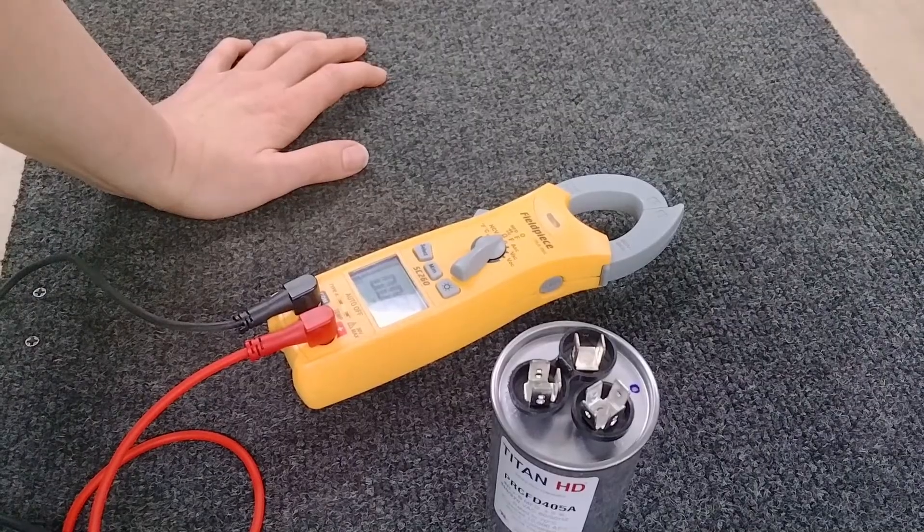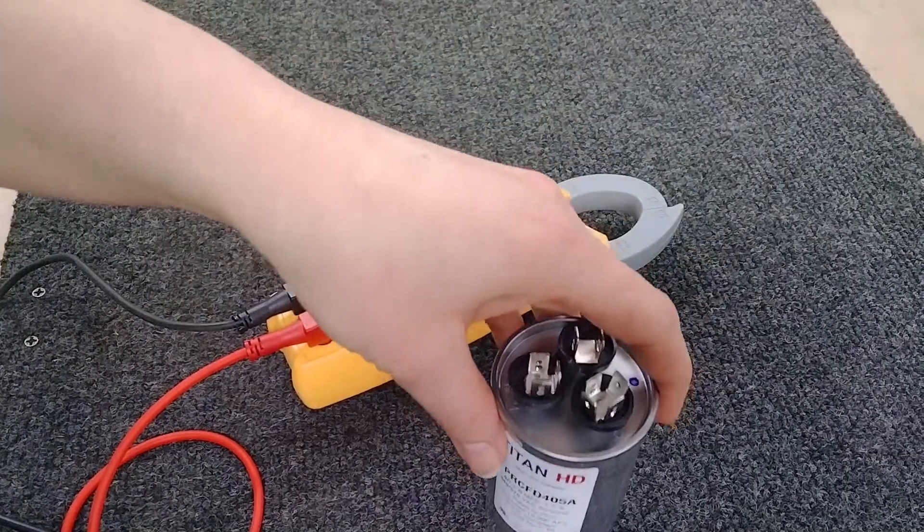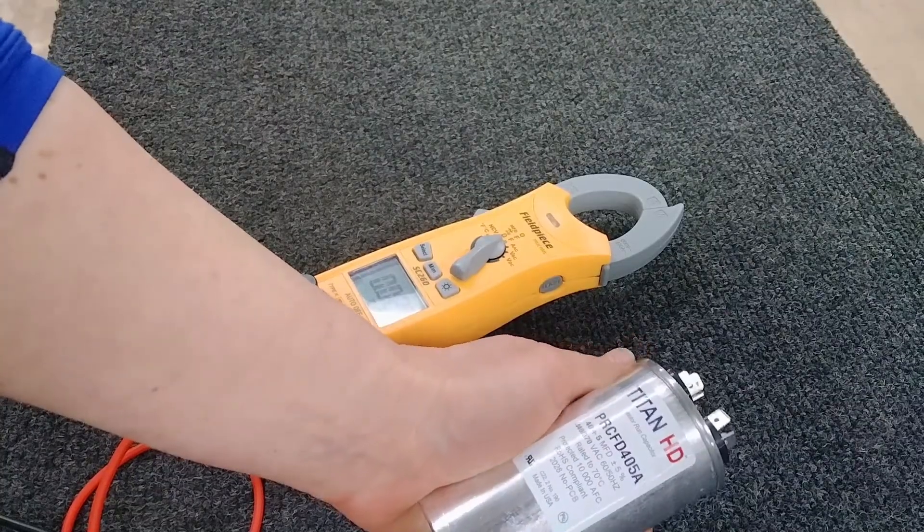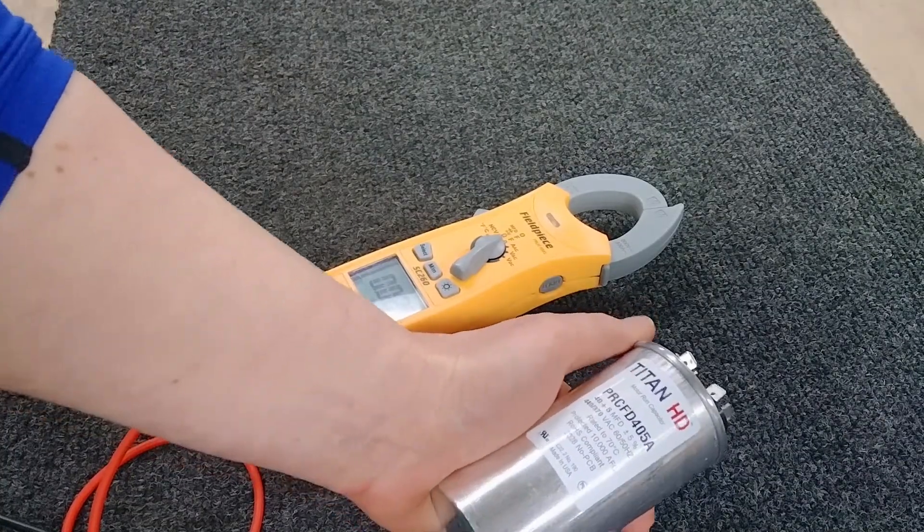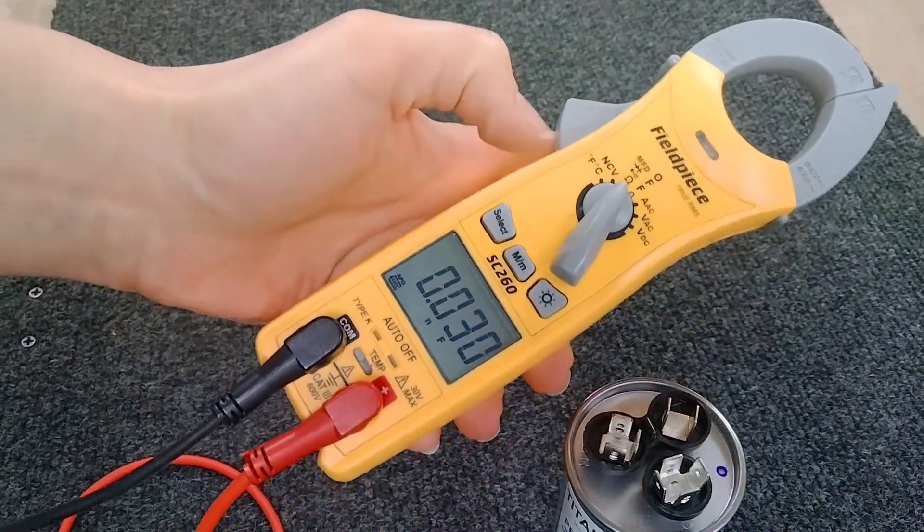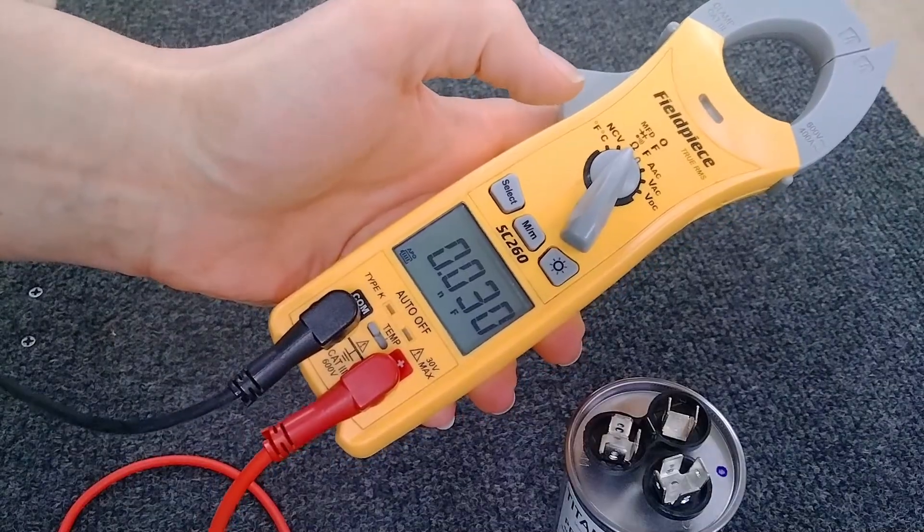Hi, this is Crystal with Open to Public HVAC Parts. Today I'm going to explain the difference between using an analog meter to check ohms versus using a clamp meter like this Fieldpiece SC260 to check your capacitance.